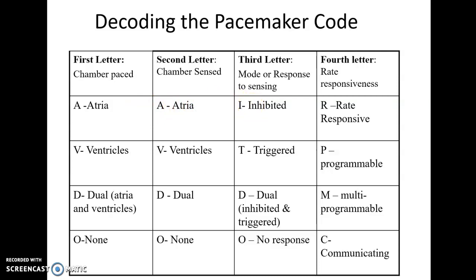If that person's atria, if their own beat is firing, it's going to inhibit the pacemaker from firing. If it has a T, it means it will be triggered by what it senses. So instead of inhibiting itself when the atria go to fire, what it's looking for is when the atria doesn't fire. It's going to give the person's own rhythm a chance to fire, and if it doesn't fire by that time, it will trigger the pacemaker to go. So it can be inhibited or it could be triggered by different settings of the machine.